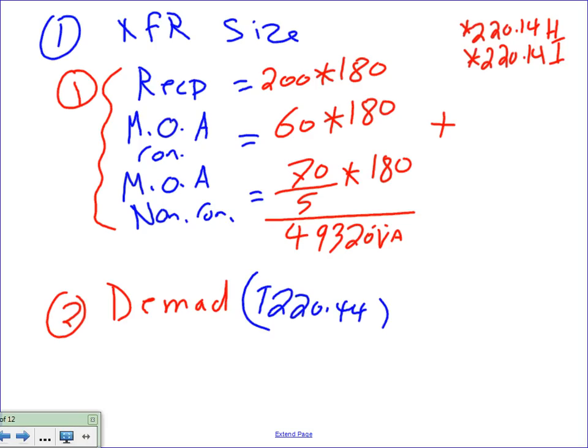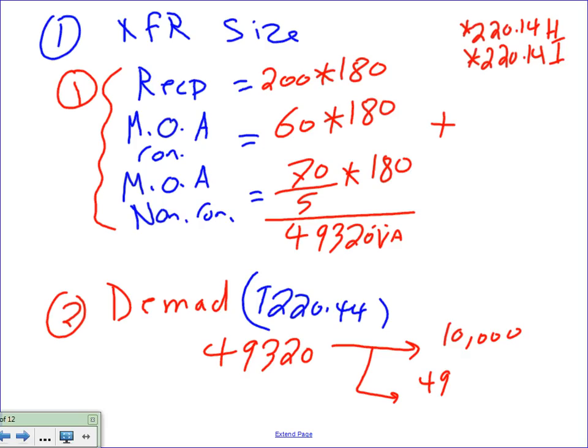Then, Chris, non-dwelling receptacles. When you do the calculation on non-dwelling receptacles, you take 220.44 and you derate them based on 220.44. I derated all of them here. So we're going to take the 49,320. From this table, the first 10,000, leave them alone. Anything higher than 10,000, which in this case is 49,320 minus 10,000, you have to cut by half. So I multiply this by 0.5, and then add them up.